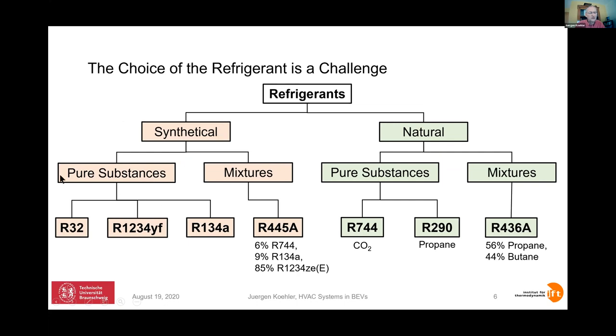For synthetically produced refrigerants, since they are produced in huge quantities and eventually end up in the atmosphere, we have to pay attention to any harmful effects on the environment, as with the first refrigerant, R12, which destroyed our protective ozone layer. Then came 134A as a replacement, but it still has such a high global warming potential that it is banned in Europe for car air conditioning applications. The replacement now is R1234YF, which is a good refrigerant for air conditioning. However, it might have some disadvantages for the heat pump mode, because the pressure is relatively low.